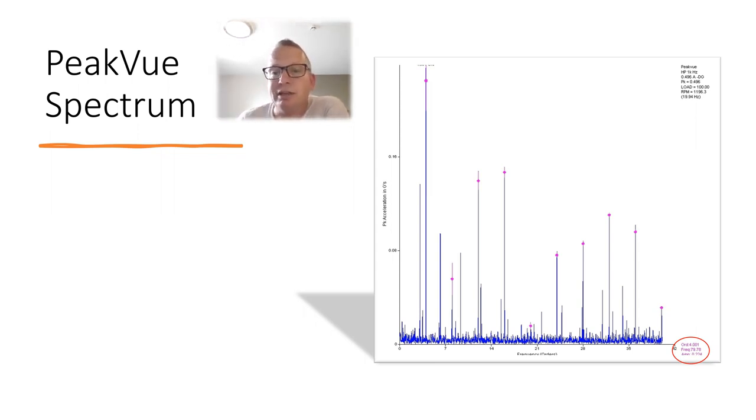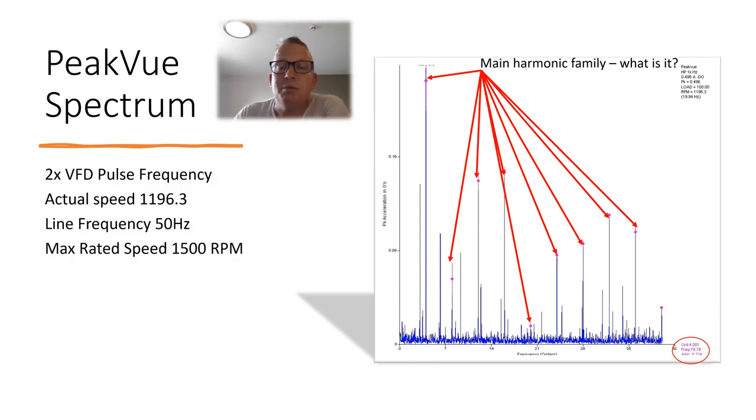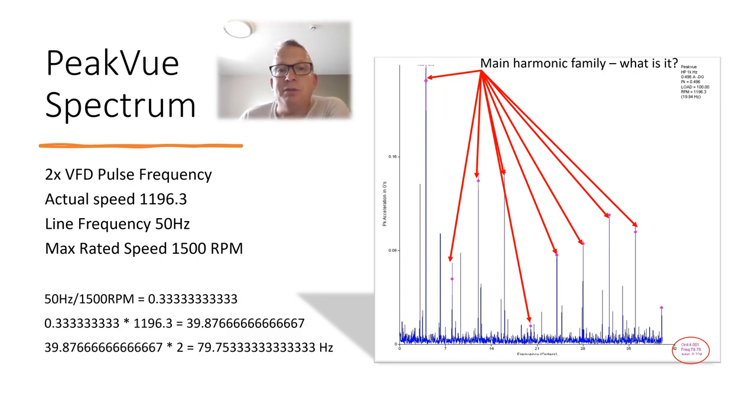So we've got this activity here and you see down here what order it's at. So what is this harmonic family? We're doing an asset assessment, is it to be of concern? Well this is a motor on a variable speed drive, so we've got the actual speed was tacked at 1196.3, 50 hertz, max rated on four poles for 1500 RPM.